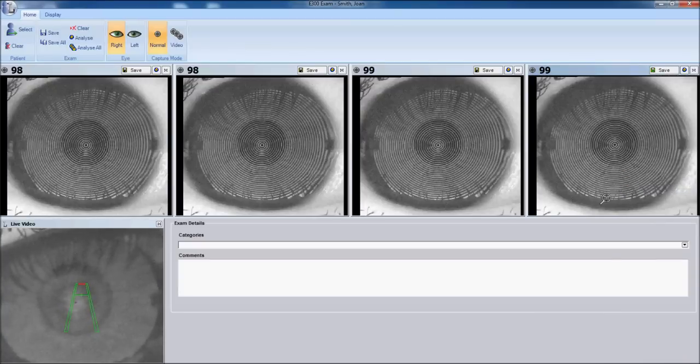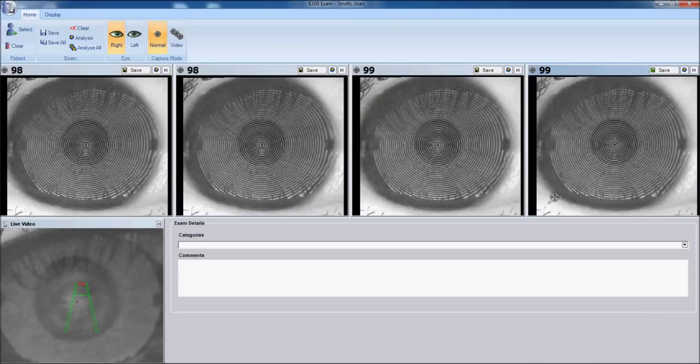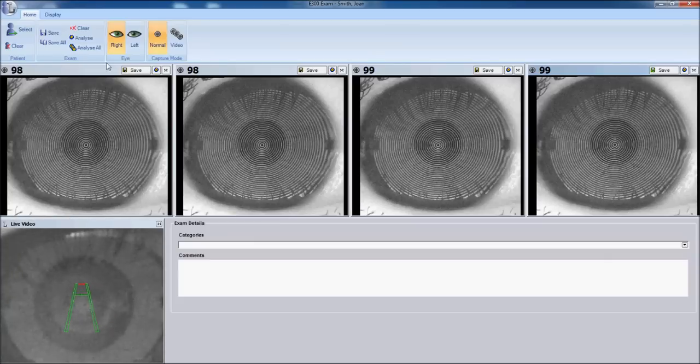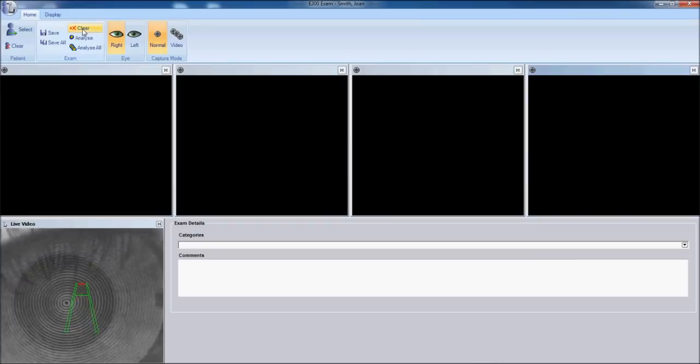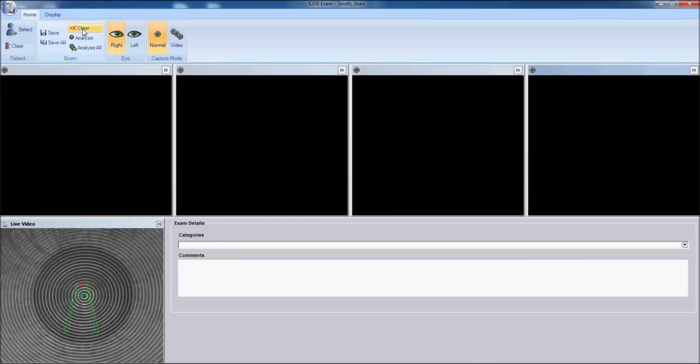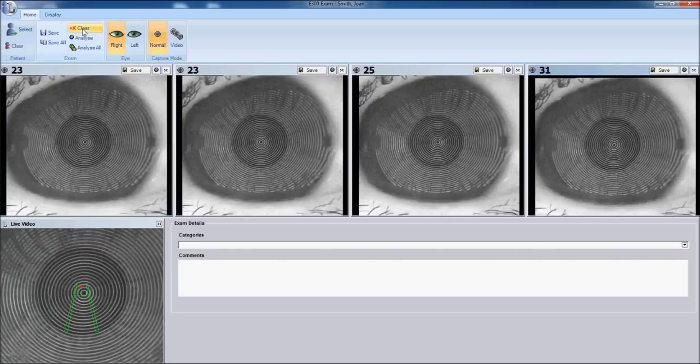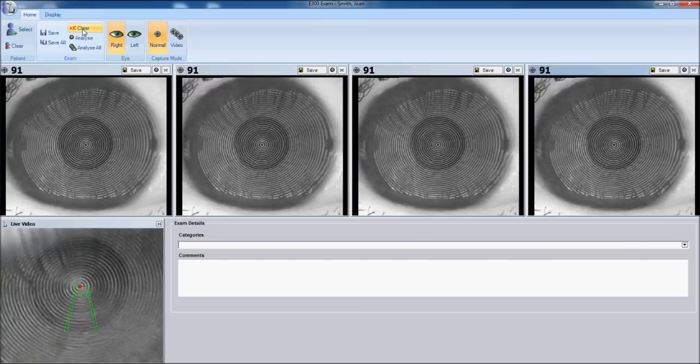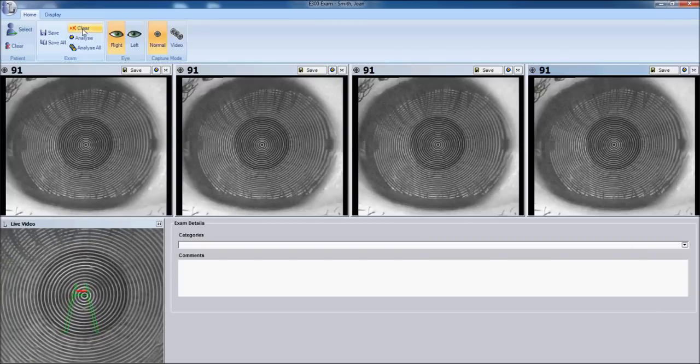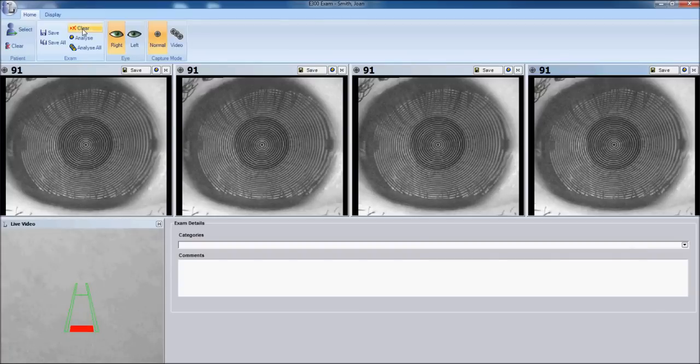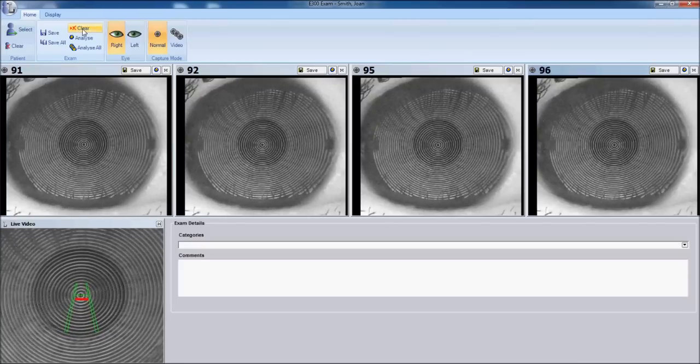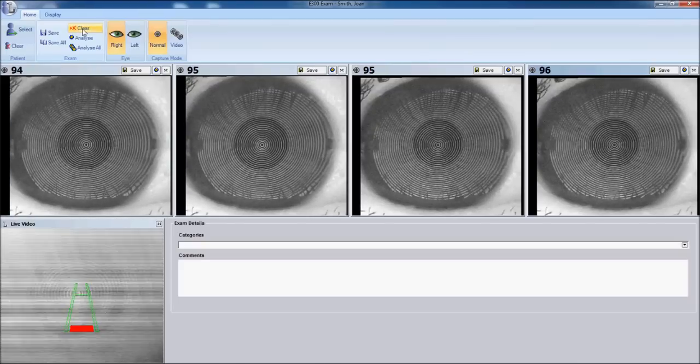If your lower lid is crossing a lot of inferior iris, you can ask your patient to reach around and pull it down. Let's click clear images. And see if we can completely eliminate the lower lid from our image. We will ask our patient to blink just prior to capture to smooth out that tear film. Notice small little tear film breakups. We will ask our patient to blink again. When you see a clear placido you can move in and take your capture.